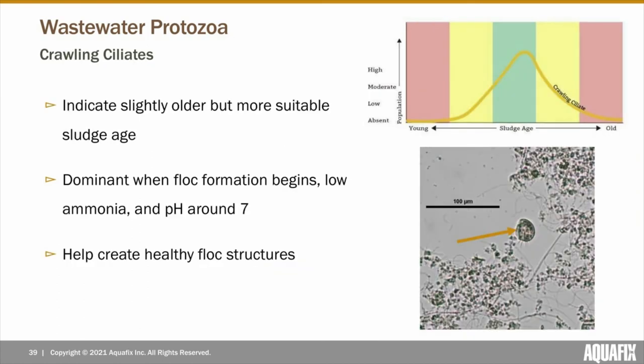Now let's move on to protozoa that are more indicative of a healthier sludge age. Crawling ciliates are indicators of an older and more sustainable sludge age, as they primarily consume floc rather than free bacteria. They're dominant when flock formation is present, ammonia levels are low, and the pH is around neutral. Crawling ciliates have actually been referred to as the cows of wastewater, as they graze on loosely attached bacteria on the edges of flock, helping to maintain a more healthy and condensed flock structure.